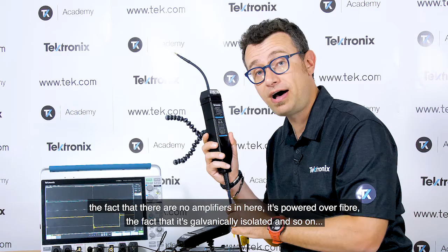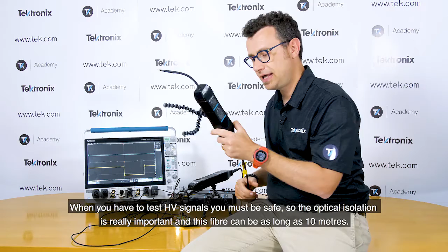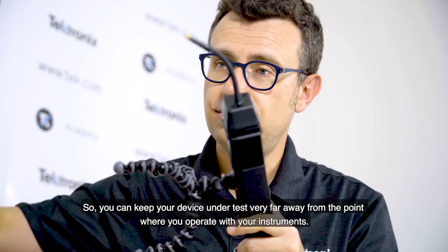But there is one aspect, safety, that for me is really important. When you have to test high voltage signals, you must be safe. So the optical isolation is really important, and this fiber can be as long as 10 meters if you want. So you can keep your device under test very far away from the point where you operate with your instruments.